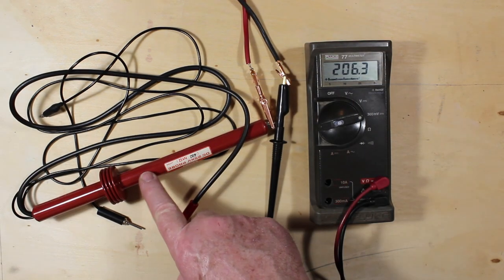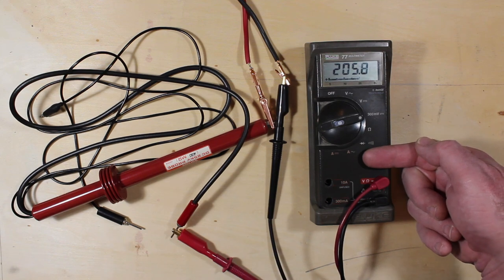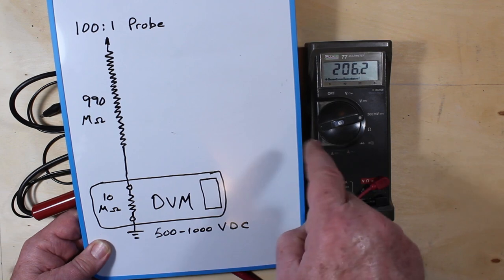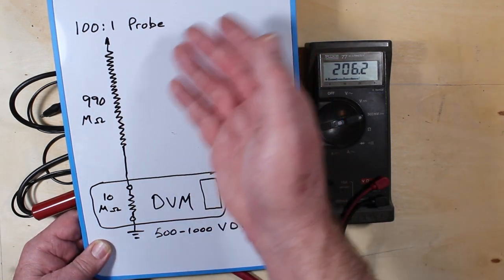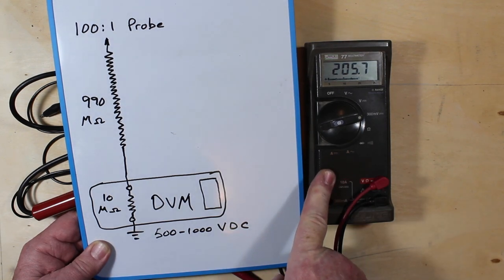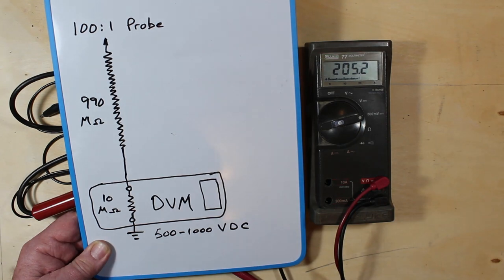So if you have a more modern high voltage probe that is designed to work on a 10 mega ohm input meter like this, this is most likely what the situation is going to be for you. You're probably going to have a 100 to 1 probe or some such, and because this is 10 mega ohm inputs, the probe itself is going to be 990 mega ohms across it.